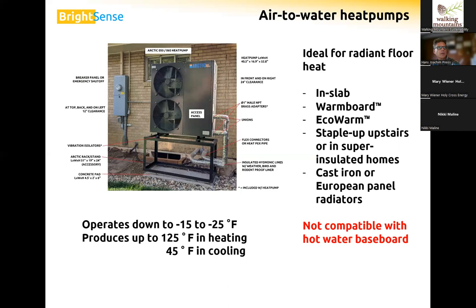And so at that point, we're basically approaching a coefficient of performance of one. And at that point, the electric resistance backup heat is the same efficiency, and so it doesn't make sense to continue operating the heat pump.